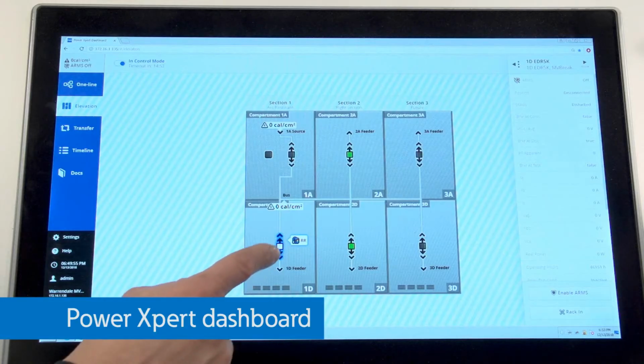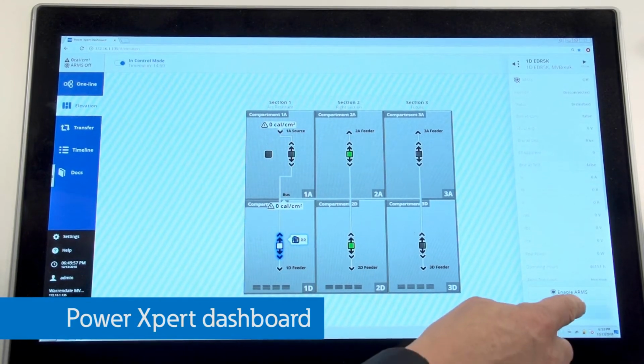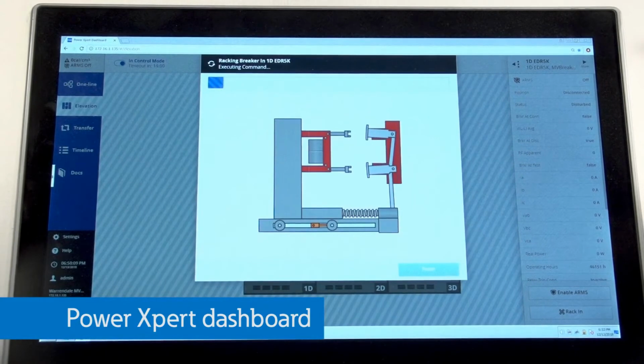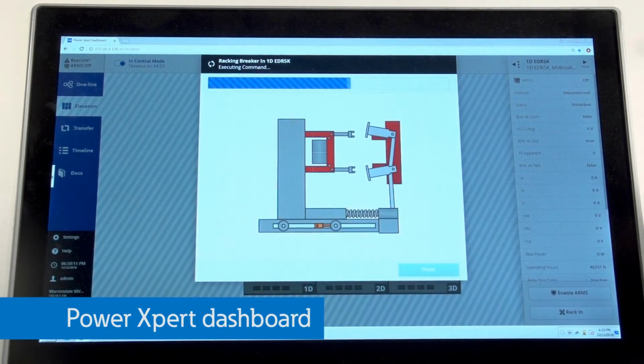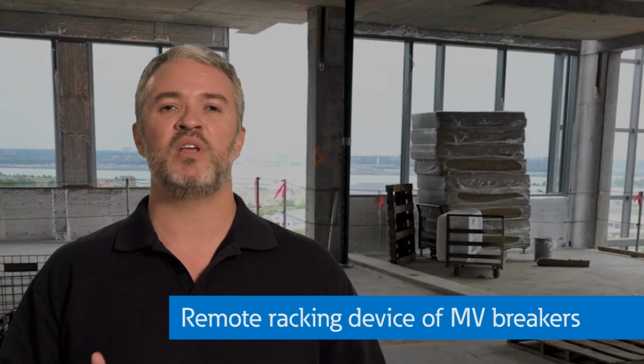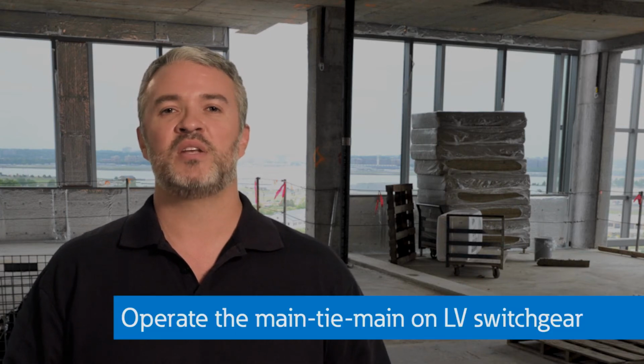This Power Xpert dashboard is a perfect solution to not only see what the arc flash levels are, but you can monitor power flow and control the equipment. As an example, hospitals can remotely rack medium voltage breakers, operate the main-tie-main on low voltage switchgear, or engage ARMS on multi-case circuit breakers with a dashboard.